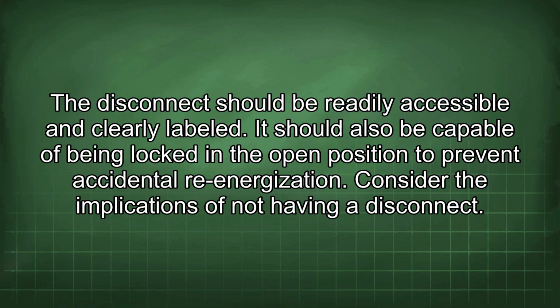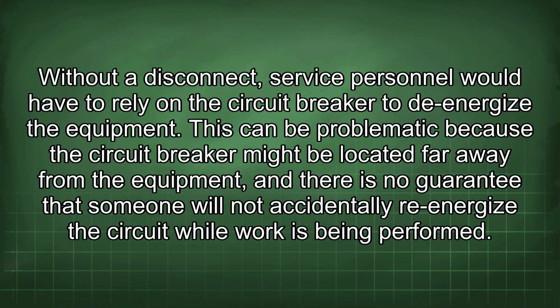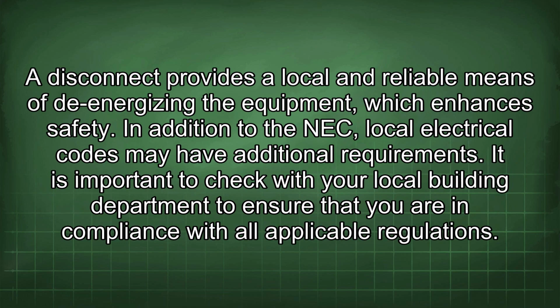Consider the implications of not having a disconnect. Without a disconnect, service personnel would have to rely on the circuit breaker to de-energize the equipment. This can be problematic because the circuit breaker might be located far away from the equipment, and there is no guarantee that someone will not accidentally re-energize the circuit while work is being performed. A disconnect provides a local and reliable means of de-energizing the equipment, which enhances safety.